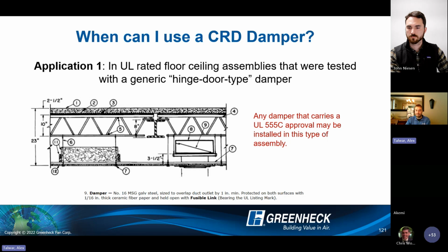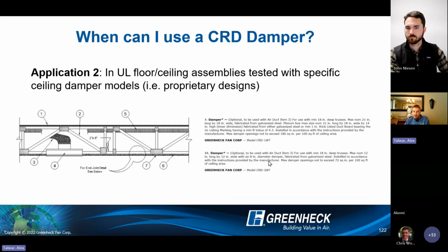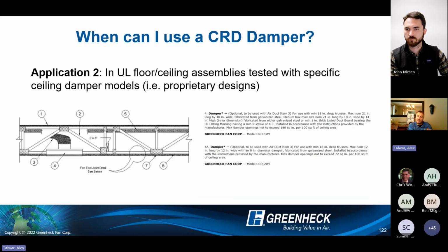So this is kind of your free for all. If you're qualified to UL 555C, you can put your damper in these types of designs that just have a generic description of a damper in it. Then we get into the more complicated ones, like the wood construction, right? So wood truss, wood joist. So designs like these are tested individually. Generally, they will list specific manufacturer and model of damper. And so if you have a design like this, you are limited to exactly what is listed in that design.